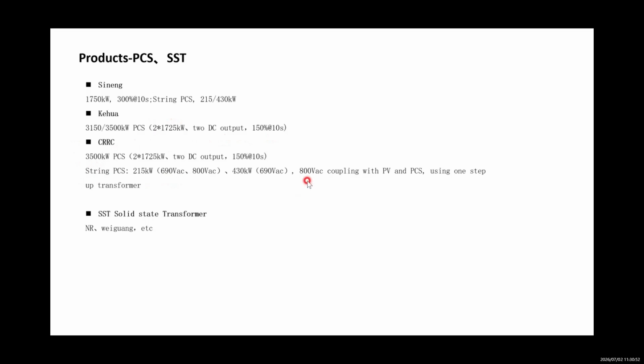As I mentioned, the 800 volt low voltage coupling with PV inverter and string PCS — CRRC claims they have solved the technical blocks for this solution, so their PV inverter and PCS can connect on an 800 volt AC bus bar, through one step-up transformer to connect to the medium voltage side. They claim to have solved all the technical blocks, for example common mode interference, DC components, and circulating current. I think this is very difficult, but CRRC believes it's no problem.